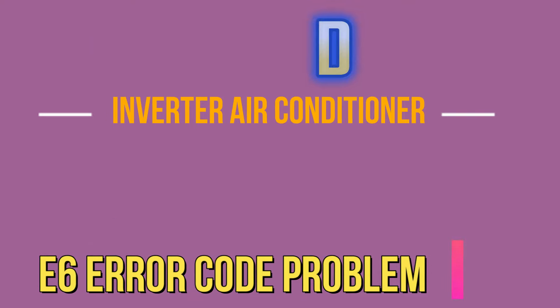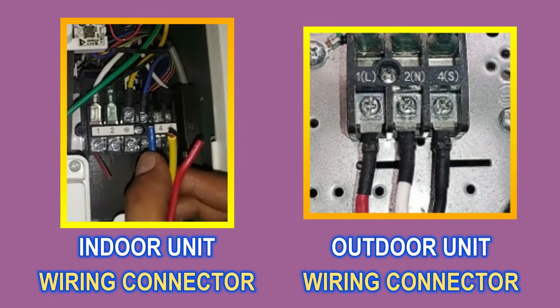This error can occur in your AC due to four reasons. The first reason may be the supply wire going to your indoor unit and outdoor unit. You should look at the connector of the indoor unit and the connector of the outdoor unit — there should be the same color code. If the same color code wire is not installed in the connectors, then you will get this error.